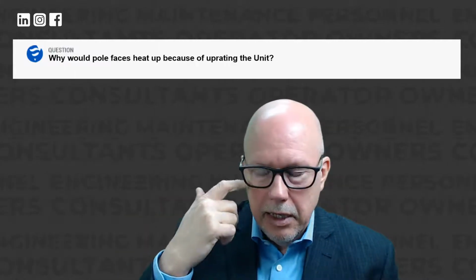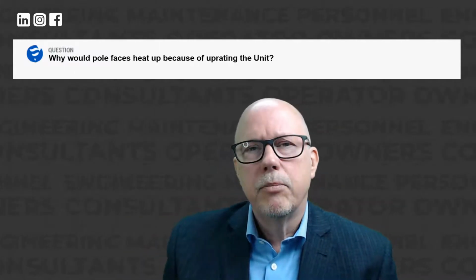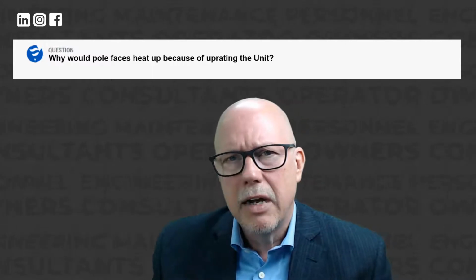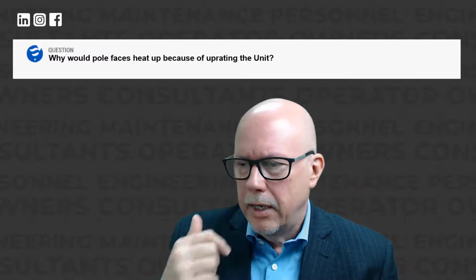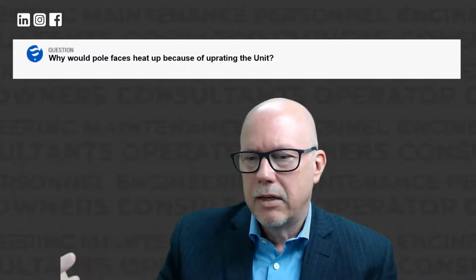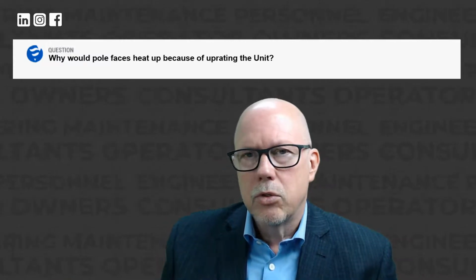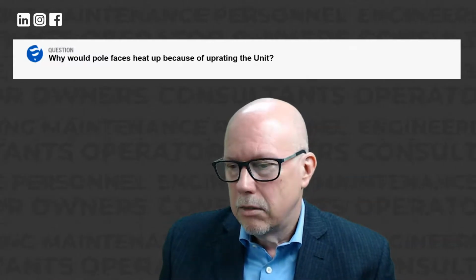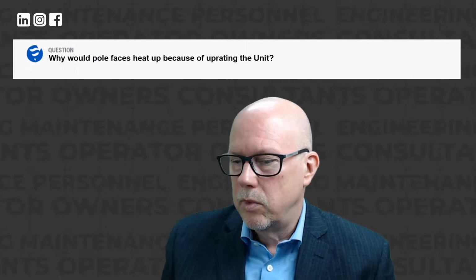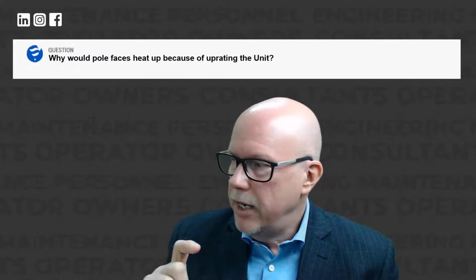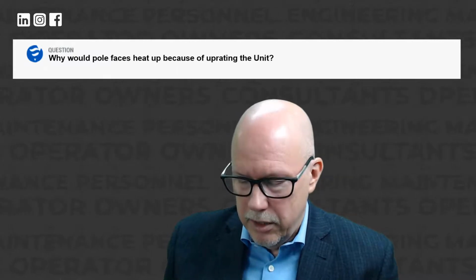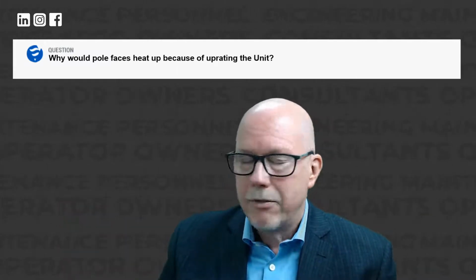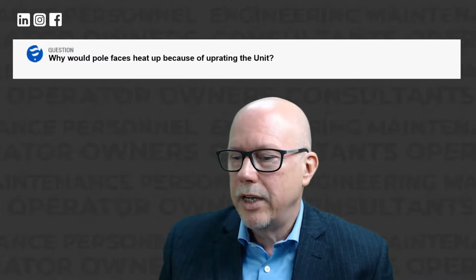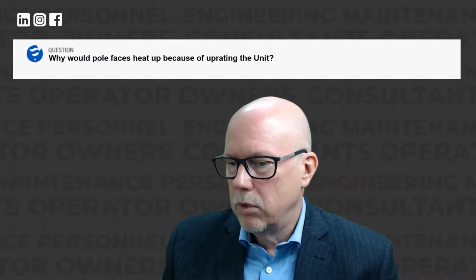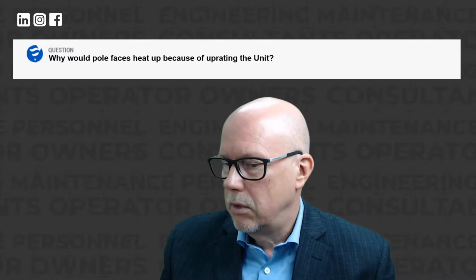We had a case in Canada where the expected pole face temperature was around 65, and after an uprating, when we went in to test, we found some poles had gone up to 105 degrees C. That was a big surprise to everyone. So if you change the electromagnetic conditions, whether through uprating or a stator that's not round, you can produce overheating poles that wear down quickly.